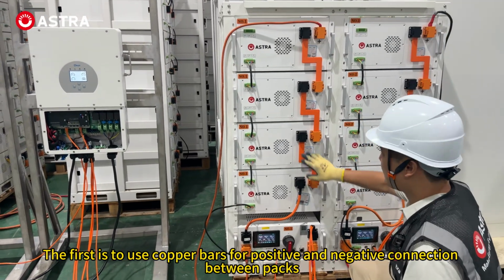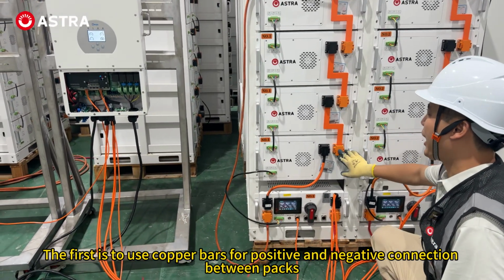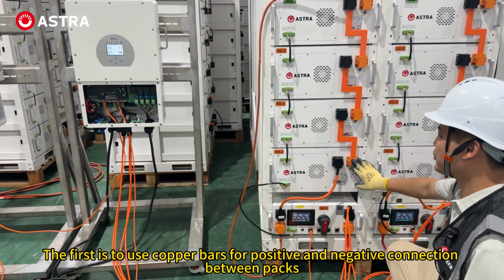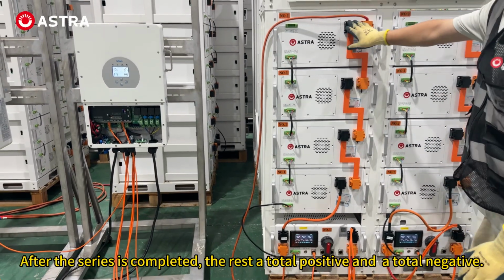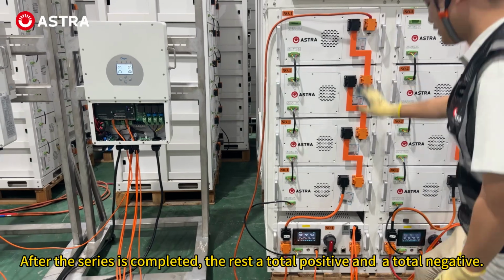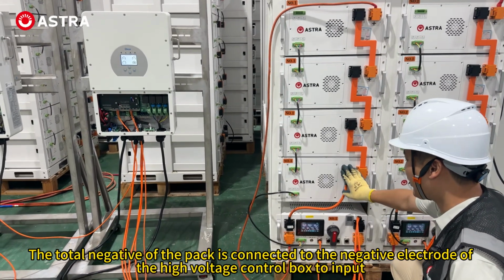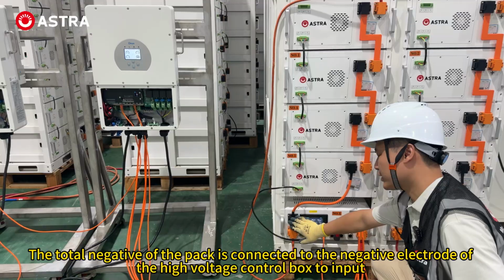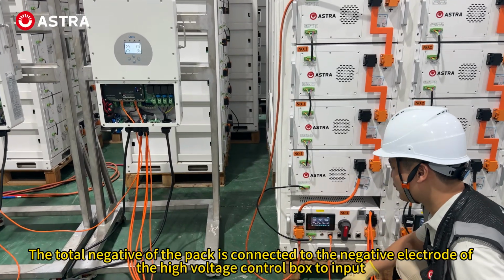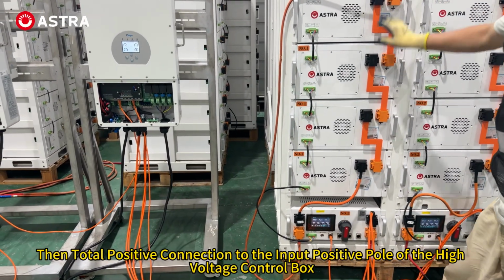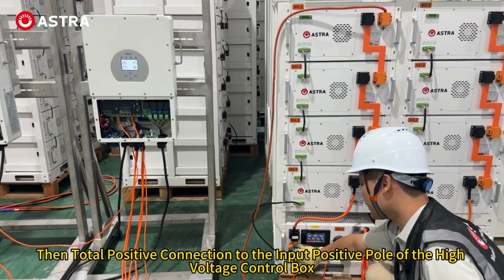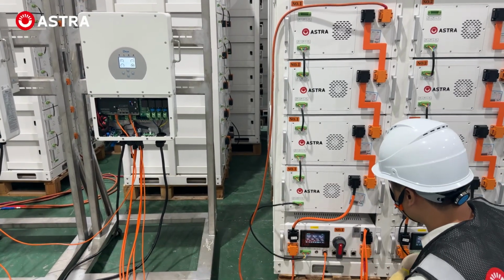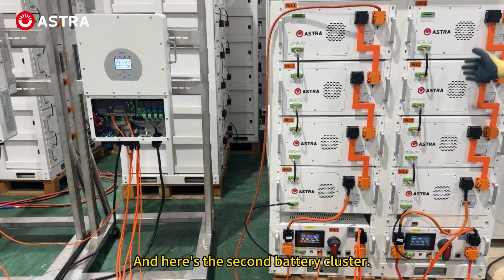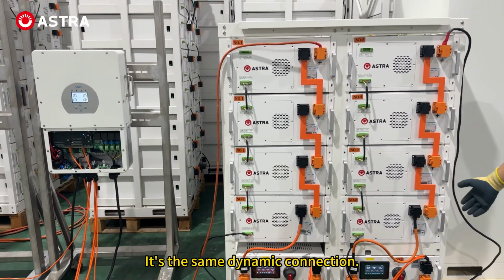The first is to use copper bars for positive and negative connection between packs. After the series is completed, there remains a total positive and a total negative. The total negative of the pack is connected to the negative electrode of the high voltage control box input. Then the total positive is connected to the input positive pole of the high voltage control box. And here's the second battery cluster. It's the same connection.